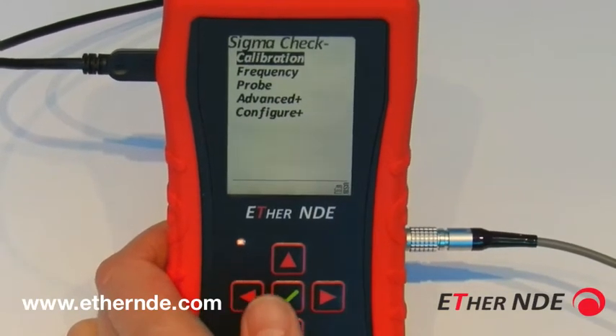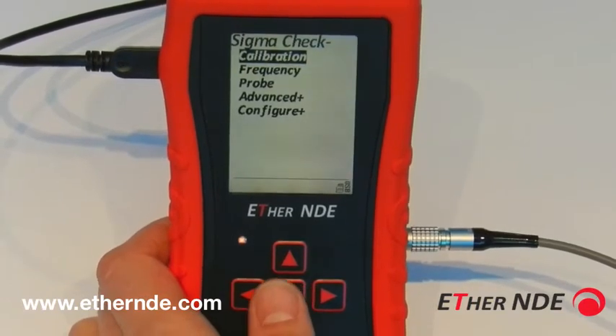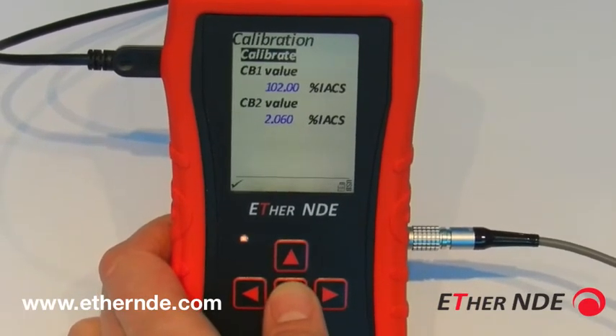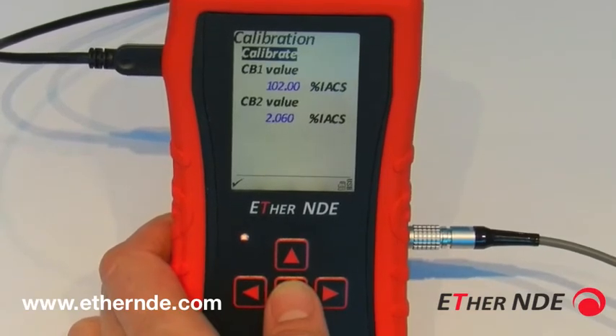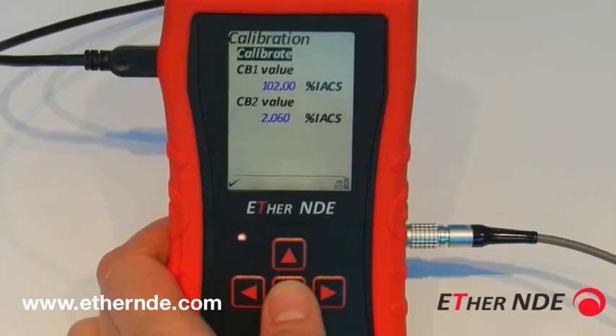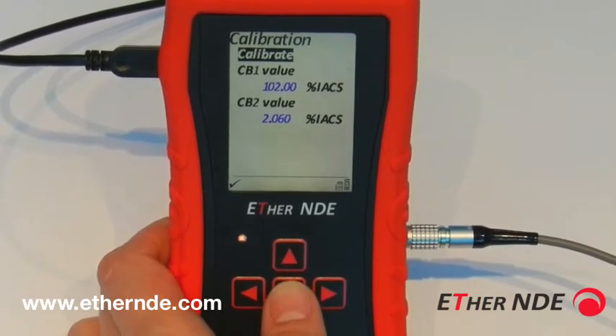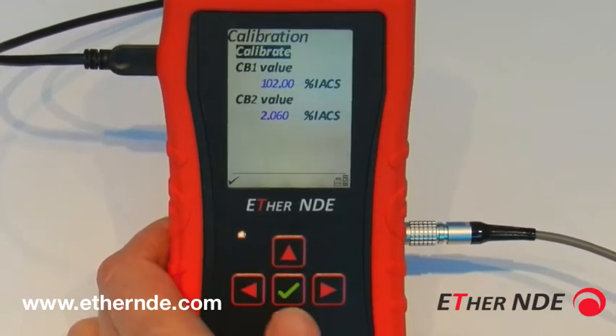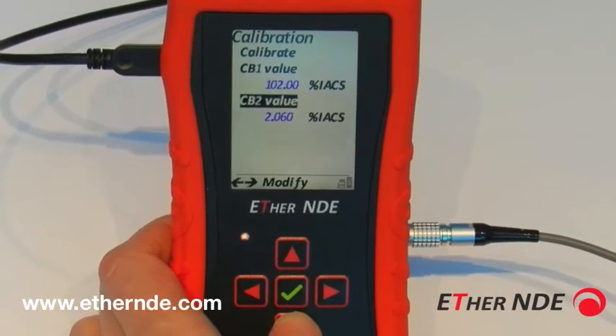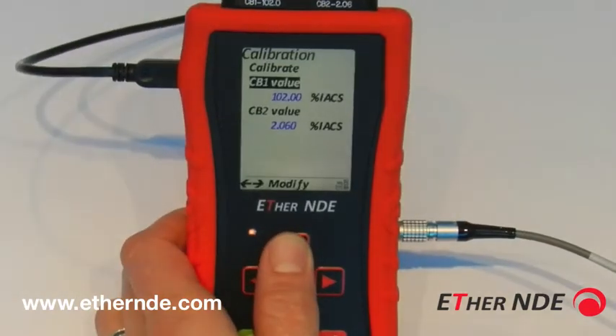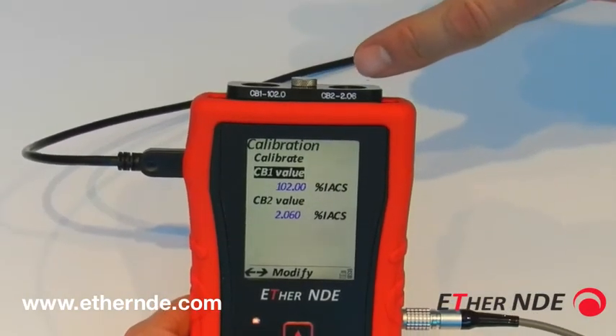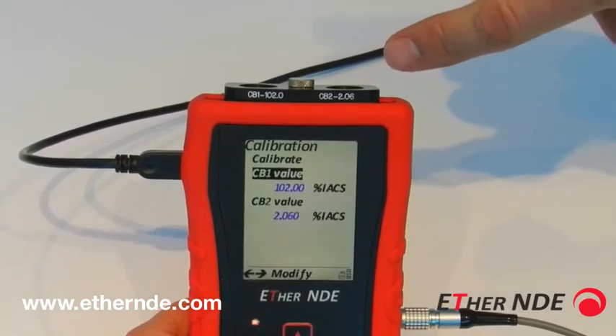Back to the Sigma check menu, the remaining item is calibration. The first menu item, calibrate, is covered in another video and is used to start the calibration routine of the instrument. The other two menu items, CB1 value and CB2 value, correspond to the value shown on the calibration block attached to the instrument, and the numbers should be identical.